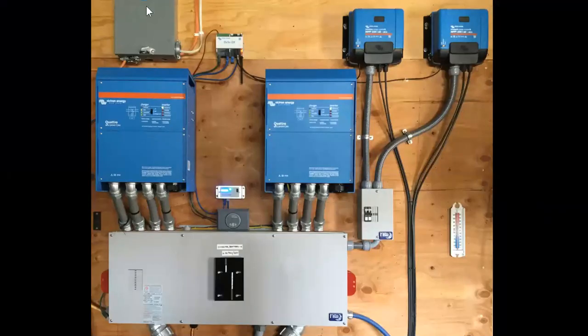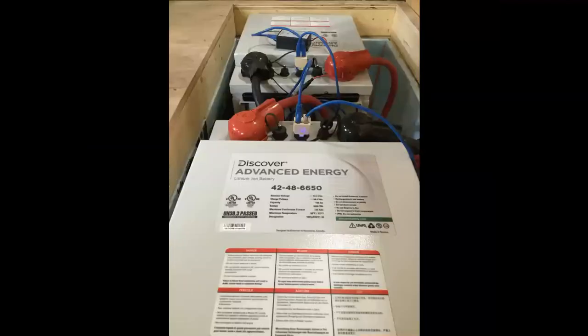Here's another shot again, you can kind of see our comm now. You can see the Lynx device here, coming out of the battery into the Lynx device and up to the GX device. I have all the MPPTs connected via VE Direct. On the battery side, this is what it looks like coming out of the power converter into the first battery, out of that battery into the second, and then onto the Lynx device.